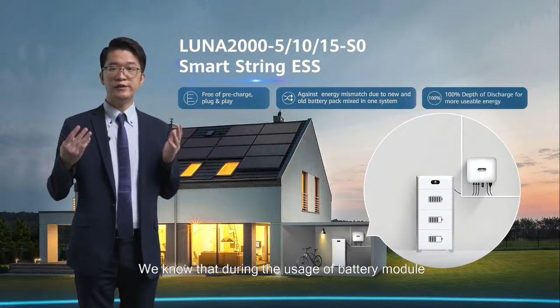We know that during the usage of battery modules, degradation occurs. So for different battery modules, they may have slightly different SOC. Or when we add a new battery module to the existing old system, the SOC difference of this new pack and old pack will be even larger. And if we do nothing in these cases, the charging of a new battery module will be limited by the older and weaker modules. For example, charging to 80% and can never go more.